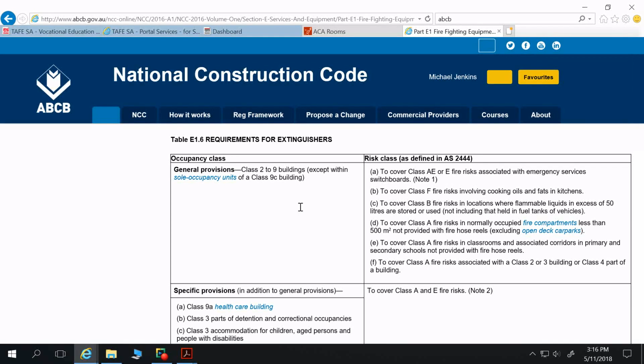So we get down here to table E1.6, requirements for extinguishers. General provisions, class 2 to 9 buildings except within sole occupancy units of a class 9C. We're not sole occupancy units in a class 9C, so we're going to have to read this bit. We need them to cover class AE or E fire risks associated with emergency services switchboards. So if we're going to have an emergency services switchboard, we have to have that. To cover class F fire risks involving cooking oils and fats in kitchens. Do either of you have a kitchen in your building? Yeah, so we're going to have to have portable fire extinguishers to cover class F fire risks involving cooking oils and fats in kitchens.